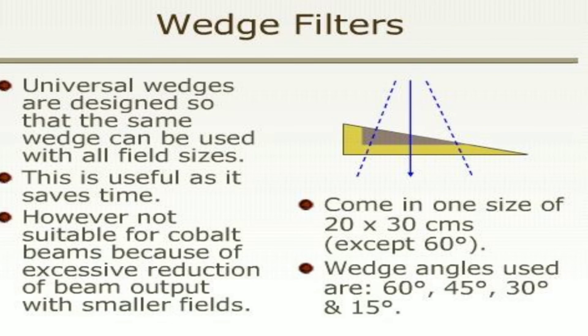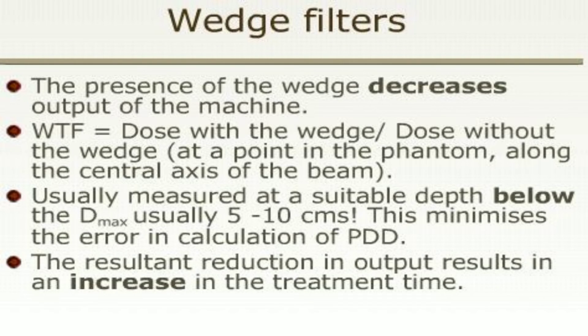Universal wedges are designed so that the same wedge can be used with all field sizes, saving time. However, not suitable for cobalt beams because of excessive reduction of beam output with smaller field size. Wedge angles used are 15 degrees, 30 degrees, 45 degrees, and 60 degrees. The presence of the wedge decreases output of the machine. Wedge transmission factor equals the ratio of dose with the wedge to dose without the wedge, usually measured at a suitable depth below Dmax, typically at 5 to 10 cm, to minimize error in calculation of percentage depth dose. The resultant reduction in output results in an increase in treatment time.